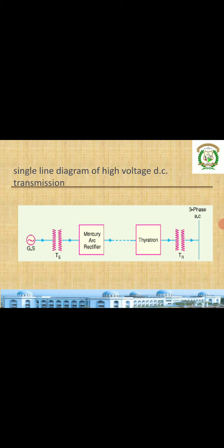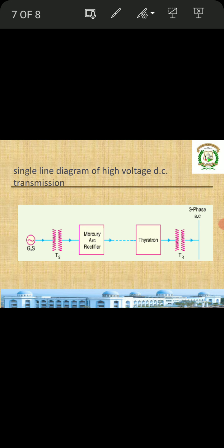The output is then taken as three-phase AC. In a DC transmission system, we require a mercury arc rectifier, thyratrons, and two different transformers. While we save on copper in between, two additional equipments — mercury arc rectifier and thyratron — are needed to rectify AC to DC and convert back from DC to AC. This is the single line diagram of high voltage DC transmission.